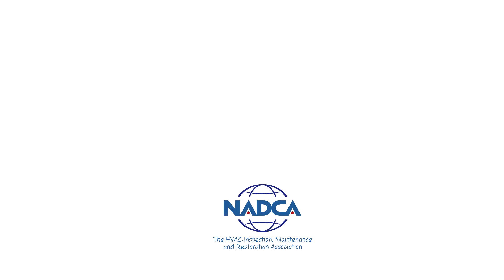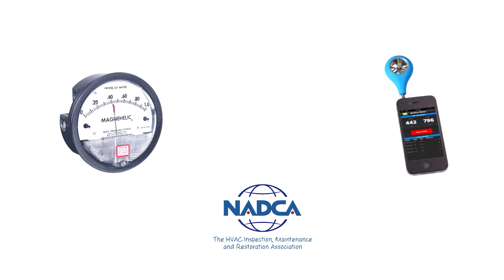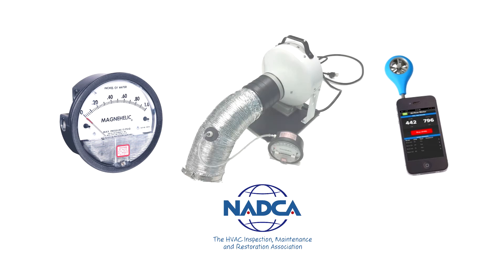To properly perform the test, be sure you have the following tools readily available: a Magnehelic gauge or digital manometer, a vane anemometer to measure airflow velocity at the termination point, along with a blower fan built to NADCA specifications to actually generate airflow through the dryer exhaust duct system.